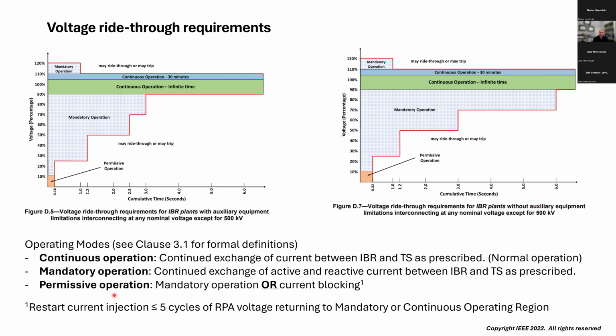Permissive operation, on the other hand, is this section when the RPA voltage goes below 10%. The requirement there is to either operate as if this is a mandatory operating mode region, or you can go into current blocking. If you go into current blocking, the caveat is that you need to restart your current injection within 5 cycles of the RPA voltage getting back into the mandatory or continuous operating range. The next couple slides, I'll talk about this mandatory operating range.